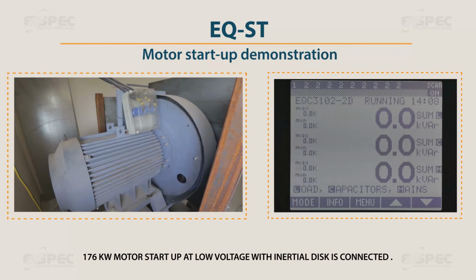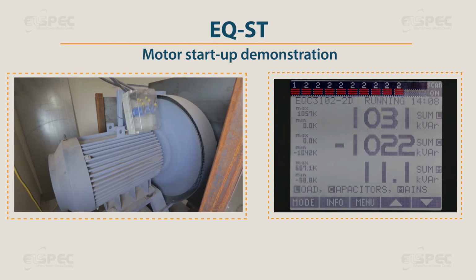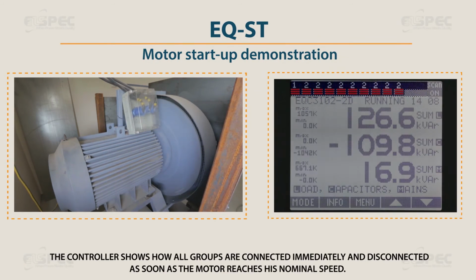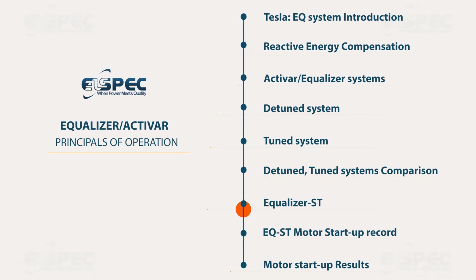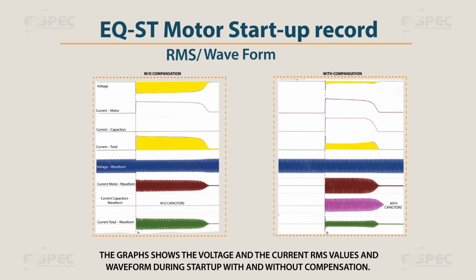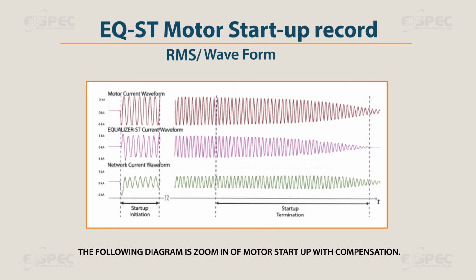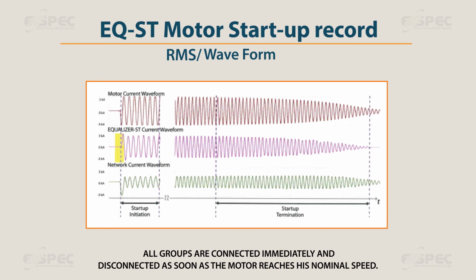The next demonstration is a 176 kilowatt motor startup at low voltage with an inertial disc connected. The controller shows how all groups are connected immediately and disconnected as soon as the motor reaches its nominal speed. The graph shows the voltage and current RMS values and waveform during startup with and without compensation. The following diagram is a zoom in of motor startup with compensation. All groups are connected immediately and disconnected as soon as the motor reaches its nominal speed.